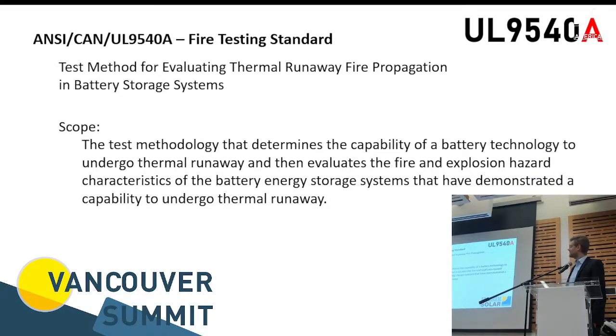So the fire testing standard, and I have on top here always the code we're referring to, because we refer to quite a few different codes and testing standards. So in this case, the UL 9540 with the A at the end is the fire propagation testing that is required to actually do the higher level system certification to the UL 9540 without the A. It's pretty much the methodology of testing a battery technology when it goes into a thermal runaway.